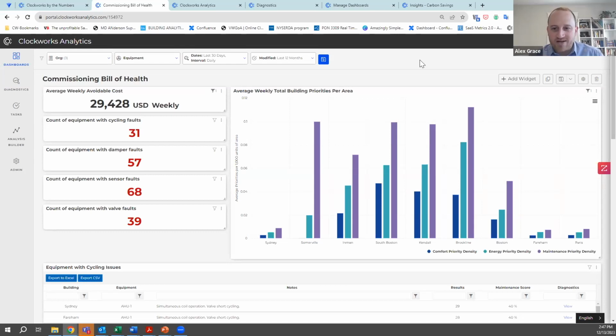Having FDD from day one really helps to reduce that finger pointing. This is an example of a dashboard that some of our clients use. We have one major client that uses it as a national standard for every building, every retrofit they do—they call it the commissioning bill of health. It says: if we have a new building or a major retrofit, we shouldn't have any cycling faults, damper faults, sensor faults, or valve faults. And if we do, let's know about that immediately while we're under warranty, and hold vendors accountable during that warranty period to fix these issues.